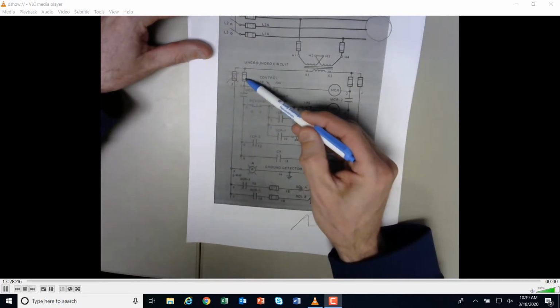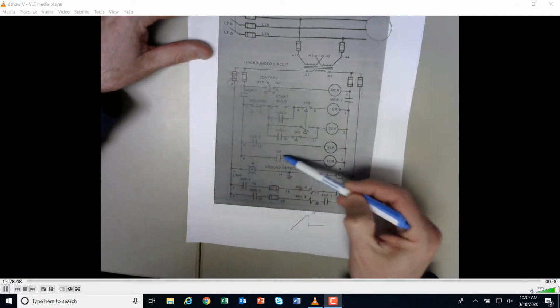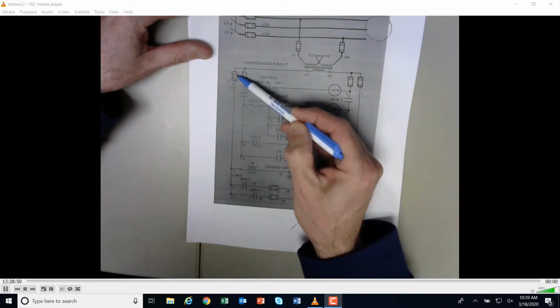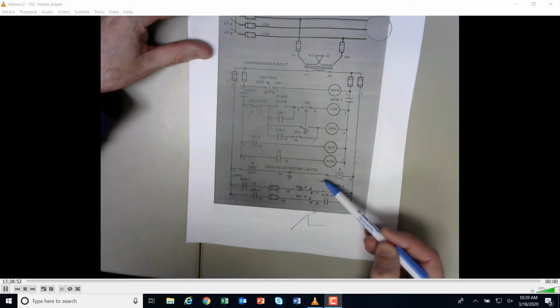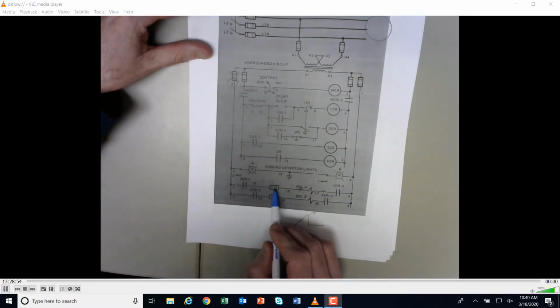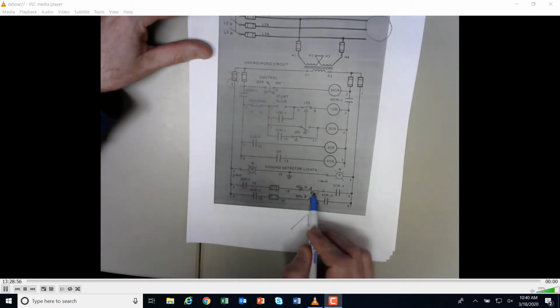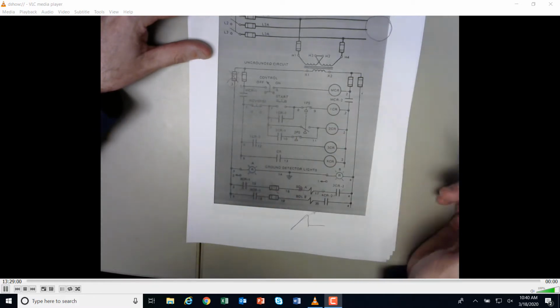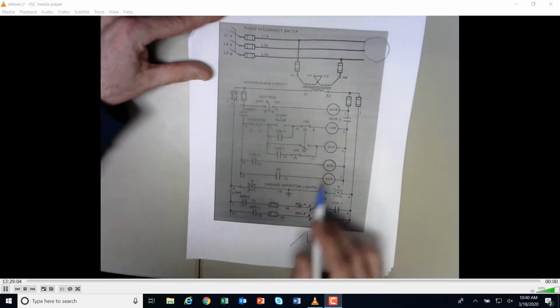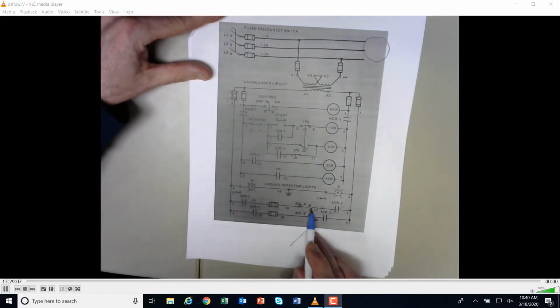So we have these fuses here that are going to bring down the complete control. These fuses here are going to bring down a portion of the process. And then the third level is the individual fuse on the device that would just bring that device down and allow quite a bit of stuff to run. So this is the highest level fuse that's going to bring everything down, and that's the lowest level fuse. It's just going to bring down the device.